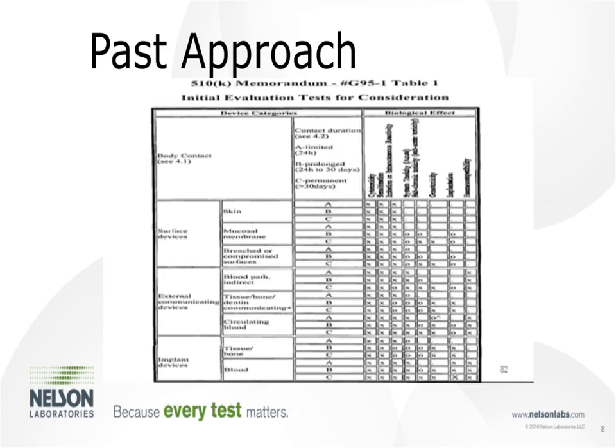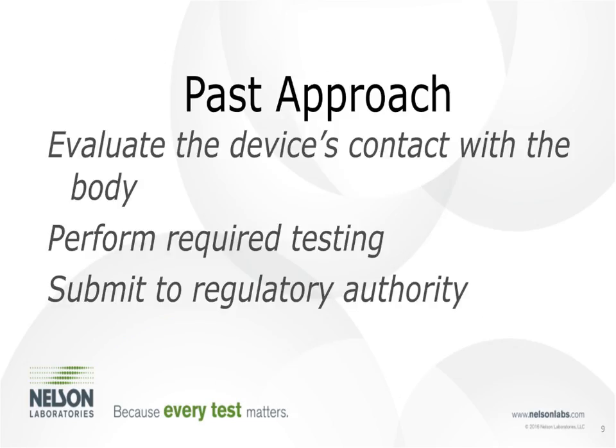The difference is those endpoints are not necessarily testing. You may be able to evaluate those endpoints with different parameters or different ways to evaluate. So that's the difference with the current revision of the guidance document from the FDA and the current draft of 10993-1. This chart has been lessened in its importance. It's no longer that checkbox, that say-all of biocompatibility that it has been.